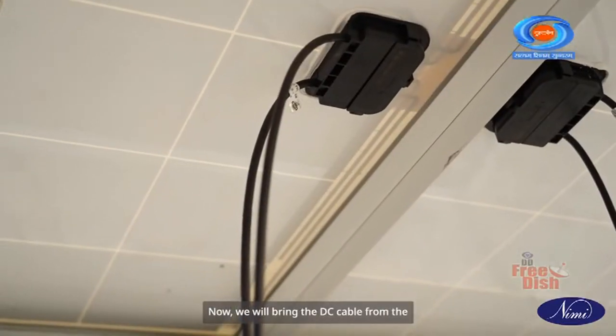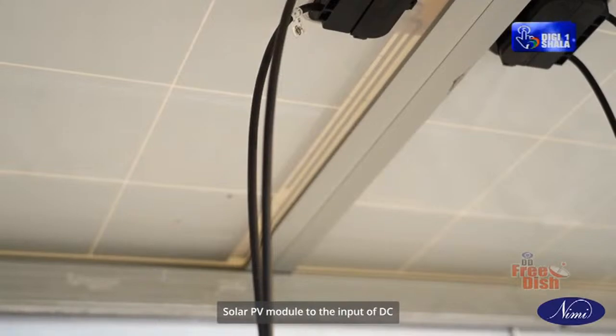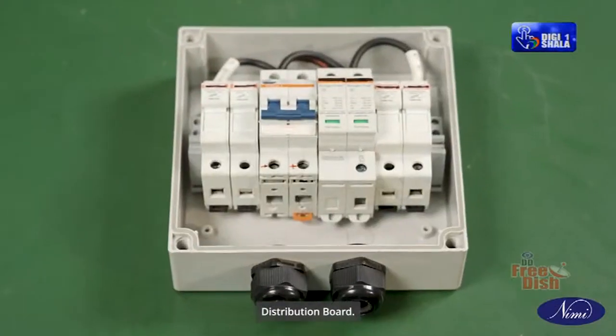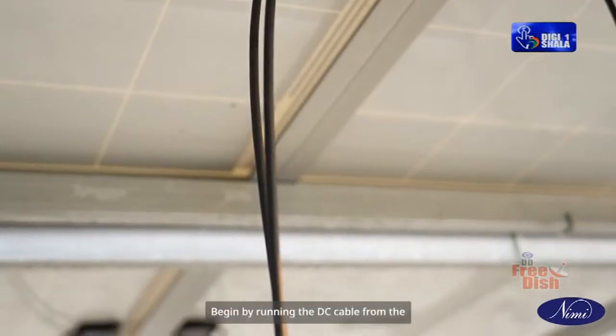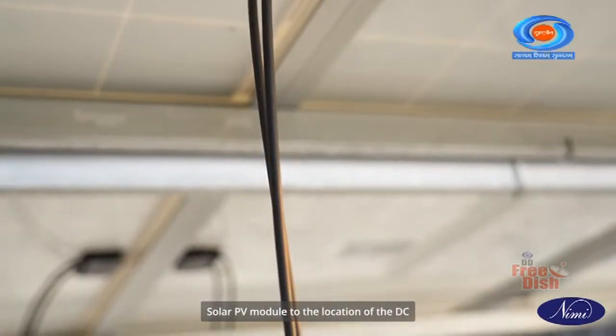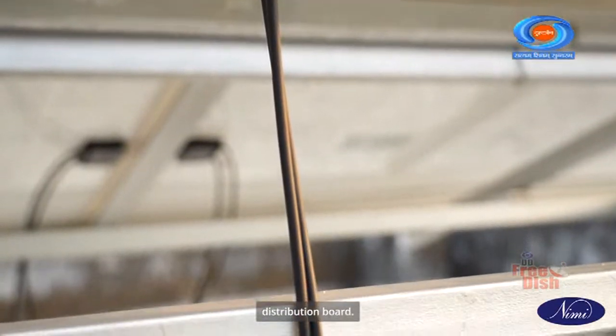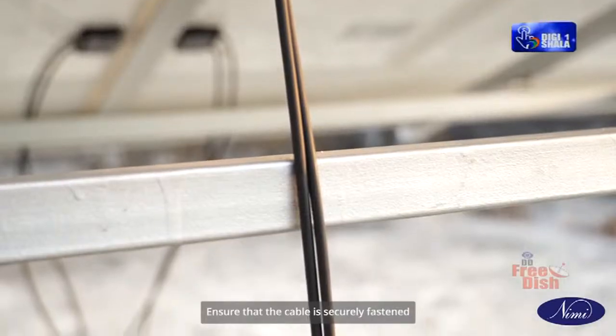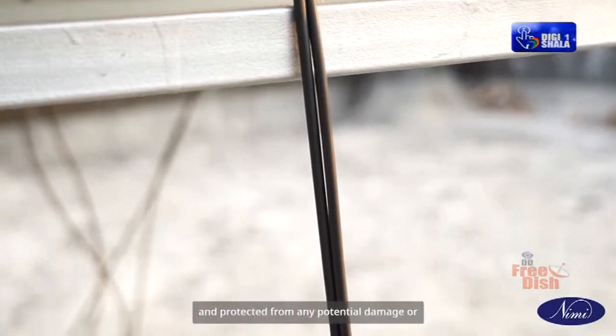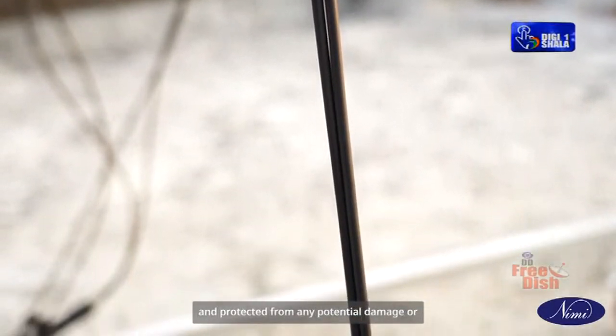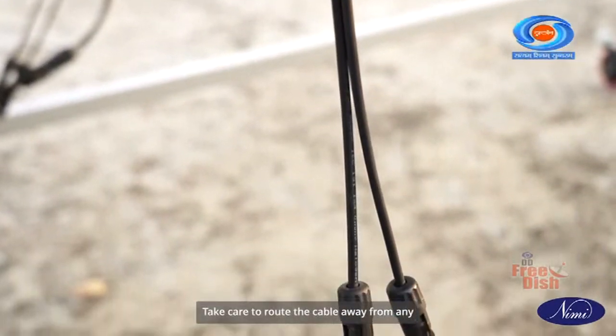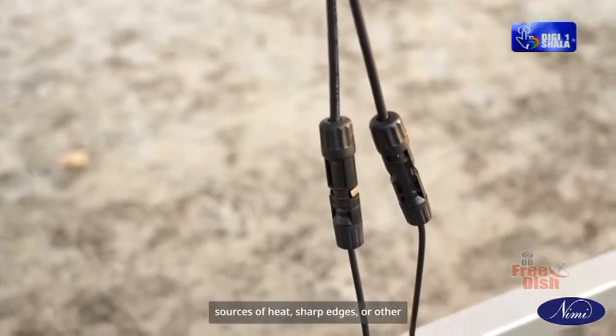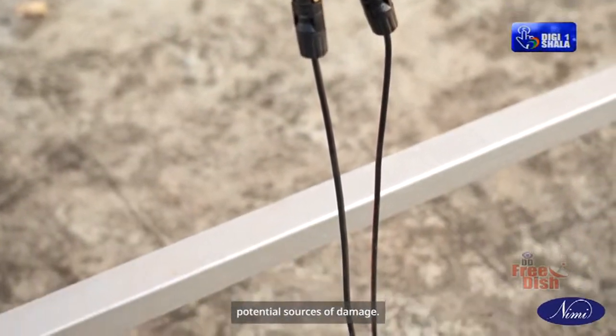Now, we will bring the DC cable from the solar PV module to the input of DC distribution board. Begin by running the DC cable from the solar PV module to the location of the DC distribution board. Ensure that the cable is securely fastened and protected from any potential damage or hazards along its route. Take care to route the cable away from any sources of heat, sharp edges, or other potential sources of damage.